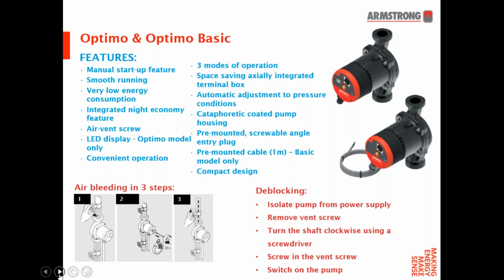As I say, one of the features that installers throughout the UK said to Armstrongs that they liked on circulators was the ability to bleed from the air vent screw in the centre of the dial. As you can see from the bottom left of this slide, air bleeding is done in three steps. The pump needs to be isolated with the isolation valve to the top of the pump. Then a screwdriver placed within the screw head, turned for around about 20 seconds, and that should alleviate most of the air, if not all of it, within the system. Turn the screw back into the closed position and then reopen the isolation valve.